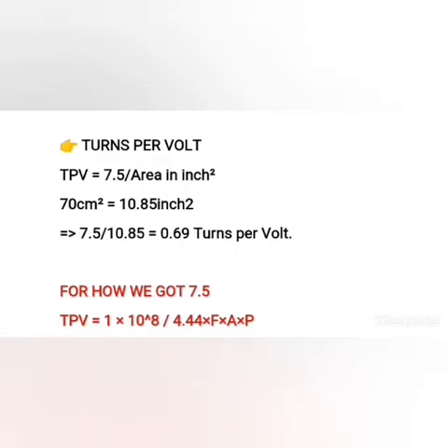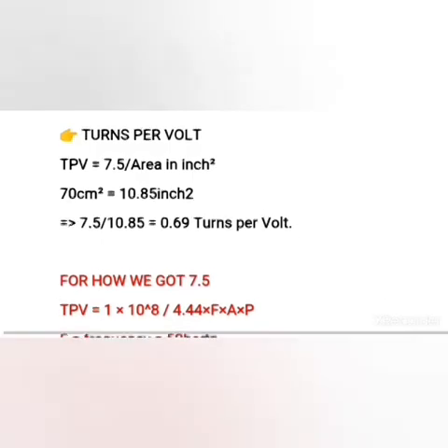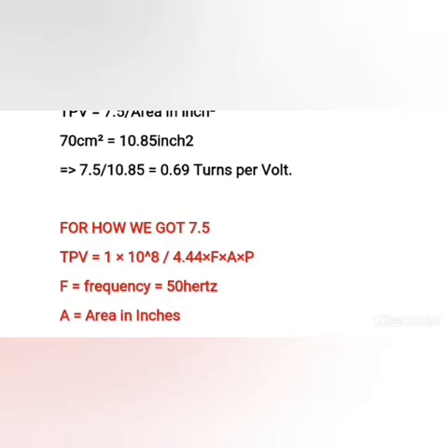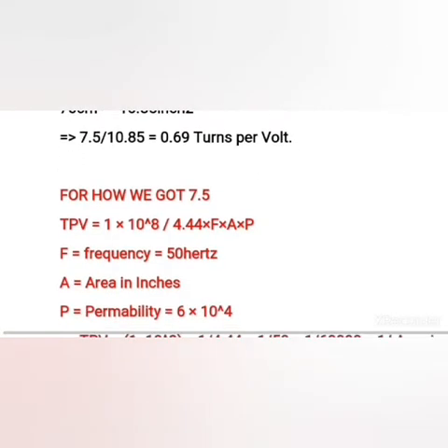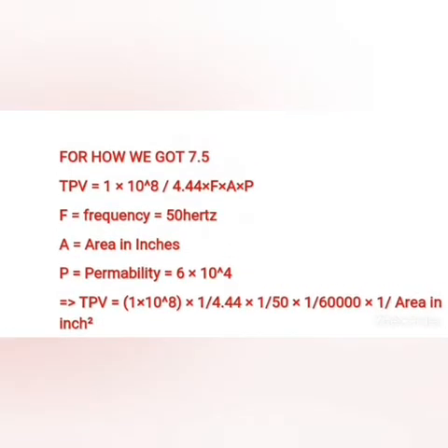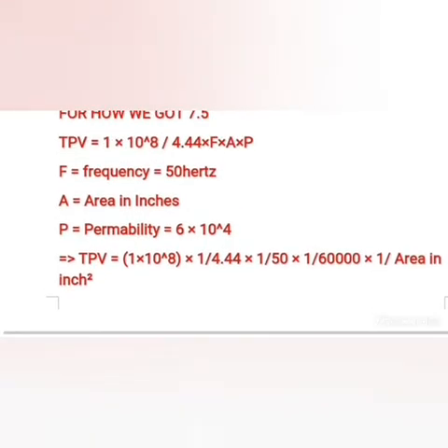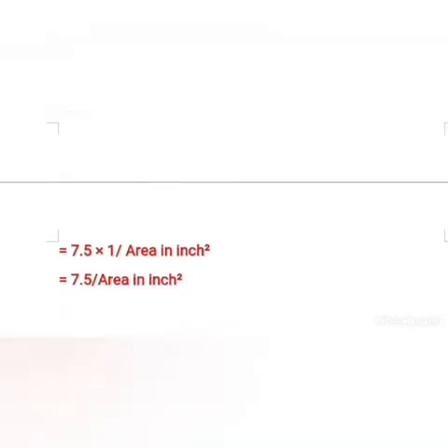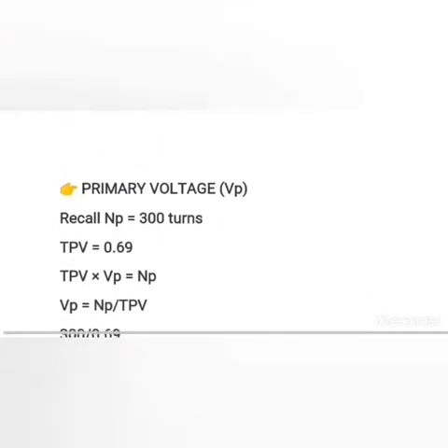The full formula for turns per volt is: 10 to the power 8, over 4.44 times frequency times area in inches squared times permeability. The frequency is mostly 50 or 60 Hz — here it is 50 Hz. Permeability is a constant, six times ten to the power of 4. When we substitute these known values — frequency, permeability, and other constants — we are left with 7.5 over area in inches, since that is the only unknown parameter. You can verify this yourself.